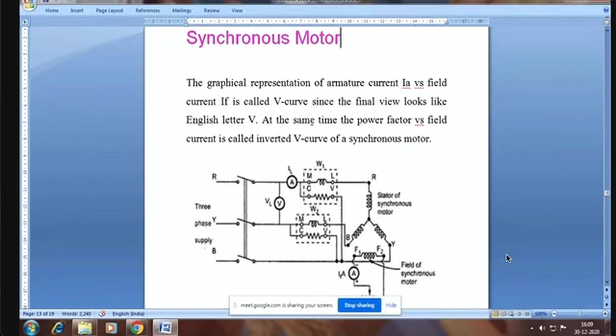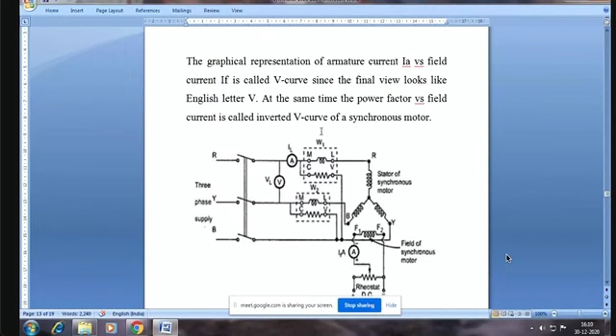At the same time, the power factor versus field current is also plotted. That means an inverted V curve is a plot of field current along the x-axis and power factor along the y-axis. In fact, we discussed in the last article that when the excitation, that is the field current, is changed, both the armature current or the stator current and the power factor will change. So obviously, when we do an experiment on a synchronous motor, we will get a lot of readings, and those readings I can plot to get both the V and inverted V curves. And the procedure to plot these two curves is given in the diagram.